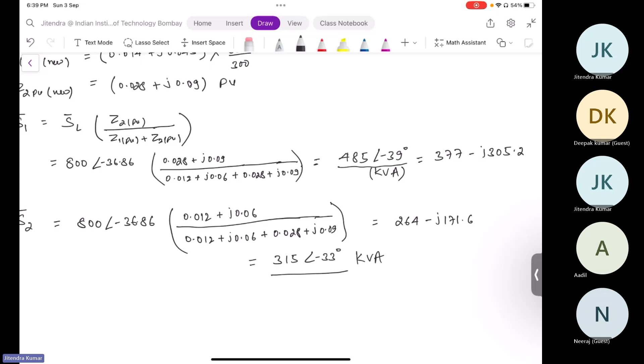Okay. Now you have the values of load sharing by both the transformers. Have you observed anything in these values? Let me simplify it for you. This transformer had the kVA rating of 600 kVA. This transformer had the kVA rating of 300 kVA. Are you able to see something? Sir, second one is overloaded. That's it. Second transformer is overloaded, and load is not shared in proportion to their kVA ratings. Because the 600 kVA transformer is supplying 485 kVA, it should have supplied close to its rating, and the other transformer rating is 300 kVA, and it is supplying 315 kVA, which means it is overloaded.